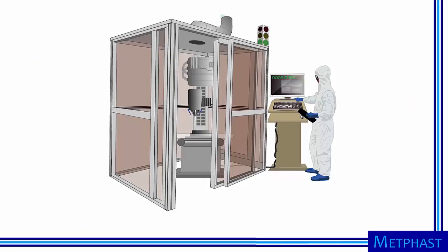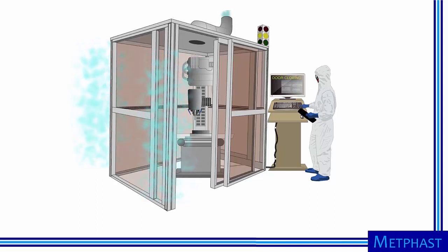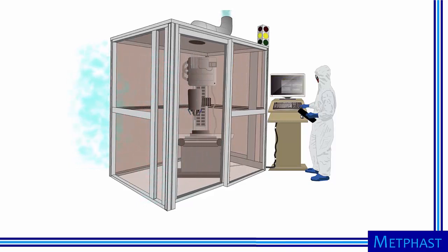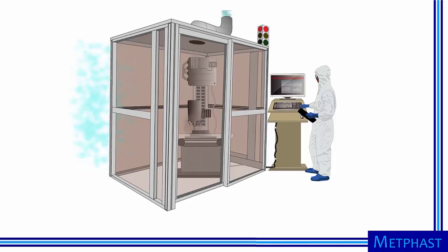Here we show a full enclosure for a machining process. The process is fully enclosed with a door that allows access to the machine for service or part change-out. Air from outside the enclosure is pulled in through any gaps. The door is essentially a large gap, and when open, air velocity into the door is slow. When the door is closed, the gaps are small and the inward velocity can easily keep contaminants inside the enclosure.